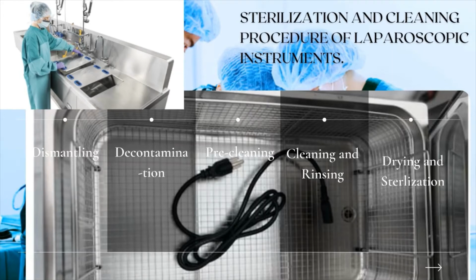Next one is cleaning. The instrument, which is designed for autoclaving, requires prior specialized cleaning and sterilization. The user ensures that no residual organic residue remains on the instrument surface, especially on instruments having several small moving parts, because it may lead to corrosive damage and pathogenic colonization.